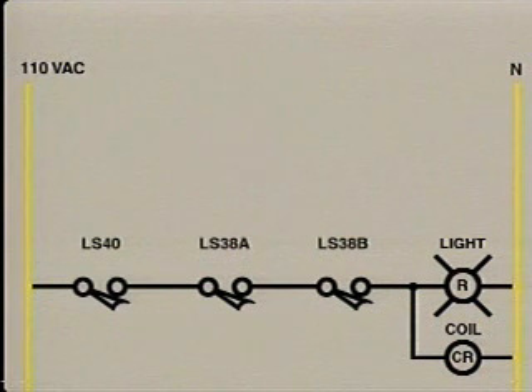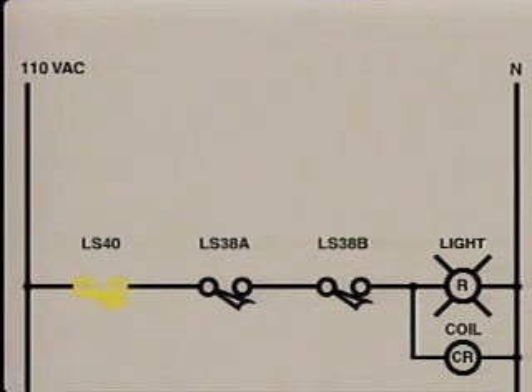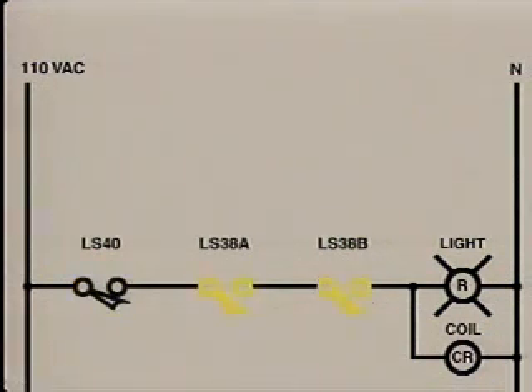The line on the left is energized at 110 volts AC, and the line on the right is connected to neutral. Limit switch LS40 is closed when the process routes fly ash from either the A collector or the B collector to the A silo. This limit switch is open when the process routes material from the bottom ash unit to the A silo. Limit switches LS38A and LS38B are open when the process is in its normal fly ash routing mode. These limit switches are closed only when the process is in the crossover mode that routes the fly ash from the B collector to the A silo.